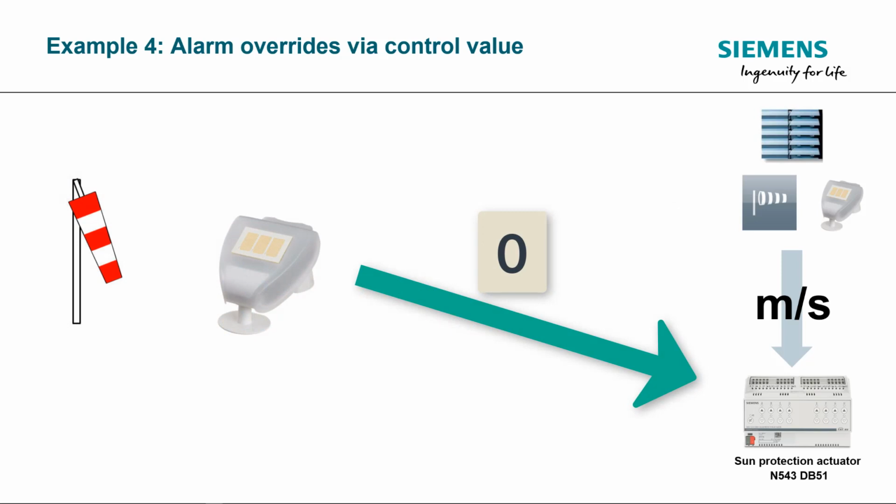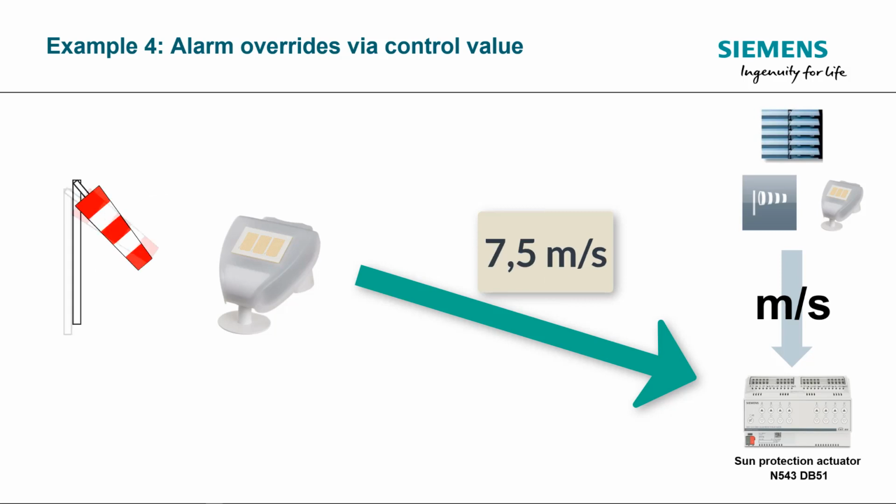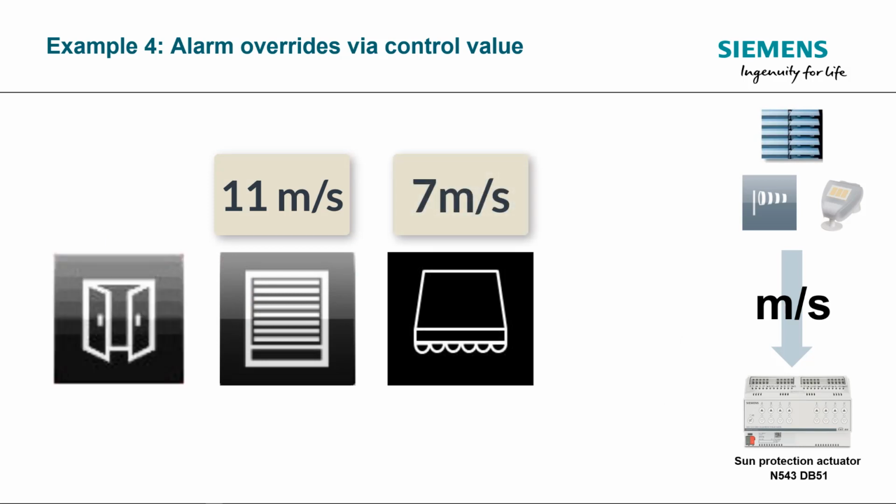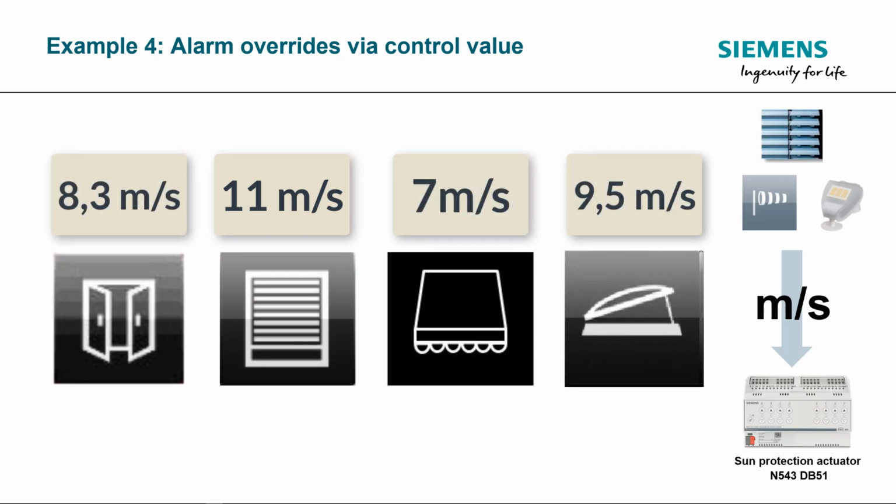Instead of the binary alarms, which are already preset via a threshold value decision in the sensor, for example in a weather central, it is sometimes more sensible or even necessary to set these thresholds directly in the actuator. It can happen that plant equipment requires more limit values for alarm override than weather sensors can provide, which generate wind, rain, or frost alarms.